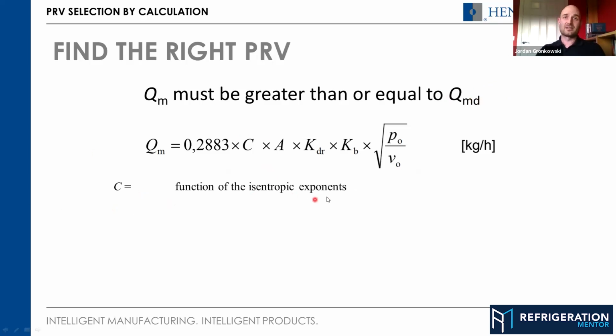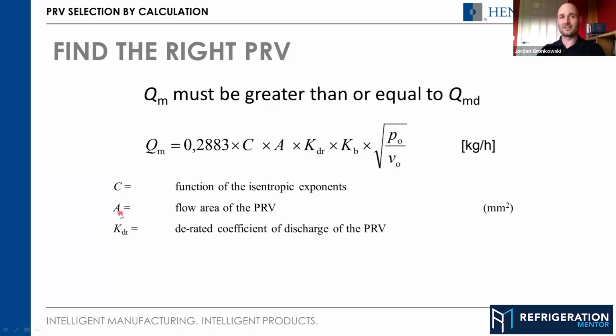C is a function of the isentropic exponent for the refrigerant, which you get in the standard for many. It can be derived from the isentropic exponent itself. Again, if you can't find it in the standard or anywhere, the refrigerant manufacturer can usually get that to you. A is the flow area of the PRV, which again, the manufacturer will have. This KDR term is specific to the European standards, and it comes from the certification of the valve when it's flow certified. Although it's specific to European standards, our valves are dual certified to both European standards and the ASME standards in America.